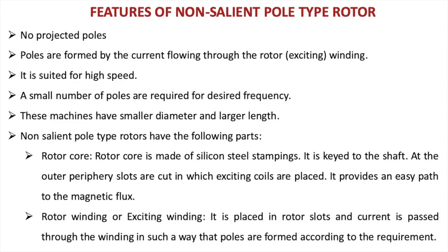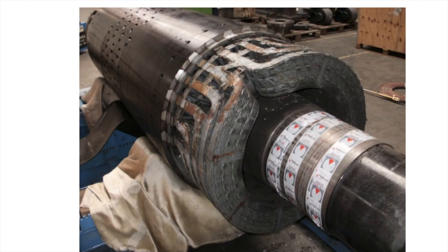While the rotor winding, or the exciting winding, is placed in the rotor slots and the current is passed through the winding in such a way that poles are formed according to the requirement of the given generator. Here you can visualize the rotor, and because it is a DC field and it is of the turbo generator, only two poles are formed.